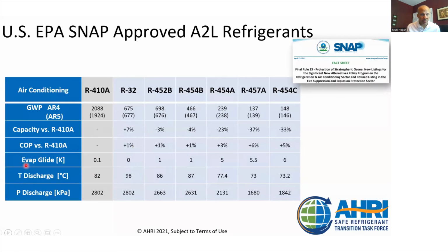Evaporator glide. This may or may not be something you guys are familiar with, primarily depending on how old you are. When I started here in the mid 90s, we were just getting used to using 410A in general as an industry. Carrier was the first one using that, and I worked at a Carrier distributor, so we were just getting involved in that. And the glide thing came up a lot. If you didn't know, any refrigerant with a 400 series number is a blended refrigerant, meaning it is two or three things mixed together to make one refrigerant, right?